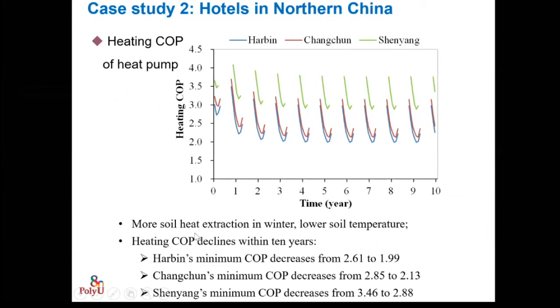So more soil heat extraction in winter means lower soil temperature, of course. Energy balance is very important for ground coupled heat pump with borehole and energy pile. You can see Harbin's minimum COP decreased from 2.6 to 1.99, but Shenyang's decreased from 3.46 to 2.88, much better.